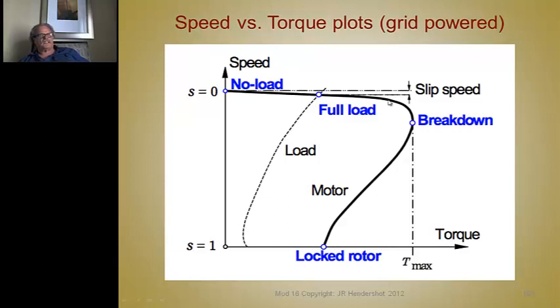And most motors, when they do stall through a load, a better way of looking at this condition is a table saw. Many of you have used a table saw, and it's powered by this kind of motor running on fixed voltage and frequency. So you are sending a board, a piece of plywood, through the saw, and you bind up the saw so the saw stalls immediately. It won't start again until you move the blade to get rid of that friction. The torque was at this level, and that's what caused it to stall. But you've got to reduce the torque to this level before it'll start again. I'm sure you've all experienced that. And that's because of the fixed frequency and voltage and the inability to control the magnetizing current. But all that can be fixed with an inverter drive, controlling the current and the torque vector.